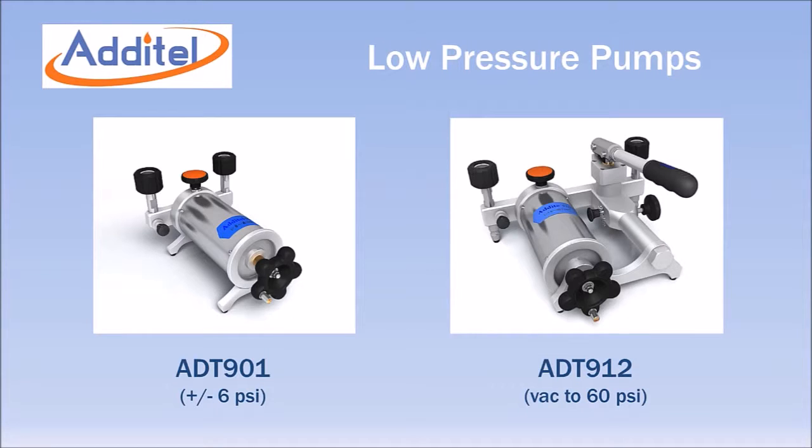The Additel ADT901 and ADT912 are specifically designed for low pressure pneumatic calibration and testing. The ADT901 covers the range of plus or minus 6 psi or 165 inches of water. The ADT912 includes the 901 pump and adds a hand operated pump assembly to extend the range to 60 psi and down to vacuum.